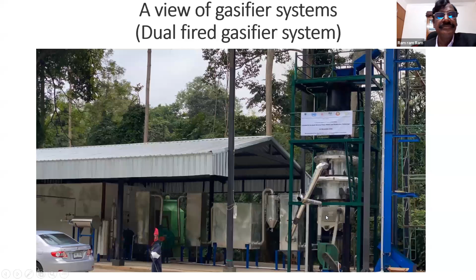The container with the ATS gasifier system is the view. It's a computer generated view, a representative view of the system. Here you see the main gasifier unit, and it has a heat exchanger. The gas that comes out of the gasifier is around 600 degrees centigrade. In all the gasifiers normally, this energy is lost. The sensible heat of the producer gas, syngas, goes into the water scrubbers particularly. Here, what we do is we take the thermal energy of the hot gas to heat the air. So the gasifier is provided preheated air at a temperature around 300, 350 degrees.